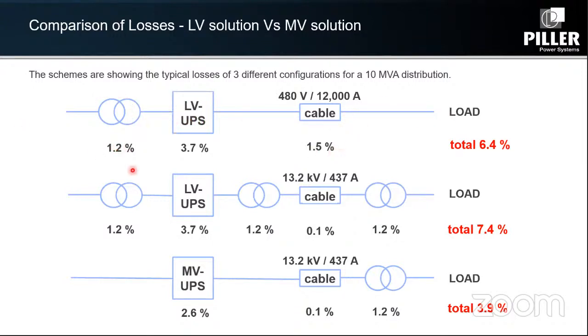So there's first the loss of the step down transformer, the loss of the UPS. We're talking about modular UPSs here, so you're talking about 96% efficiency. There is a loss on the cable. So your total loss is 6.4. If you have a 30 megawatt site and you want to save space and you want to take it on medium voltage, you could do that even with low voltage. So you would have the same loss, 1.2 for the step down. The UPS loss remains the same. You can step it up, put another transformer, add some loss. You can see the loss on the medium voltage cable, so 0.1, and then you again step it down for the data center. Your loss would be 7.4.